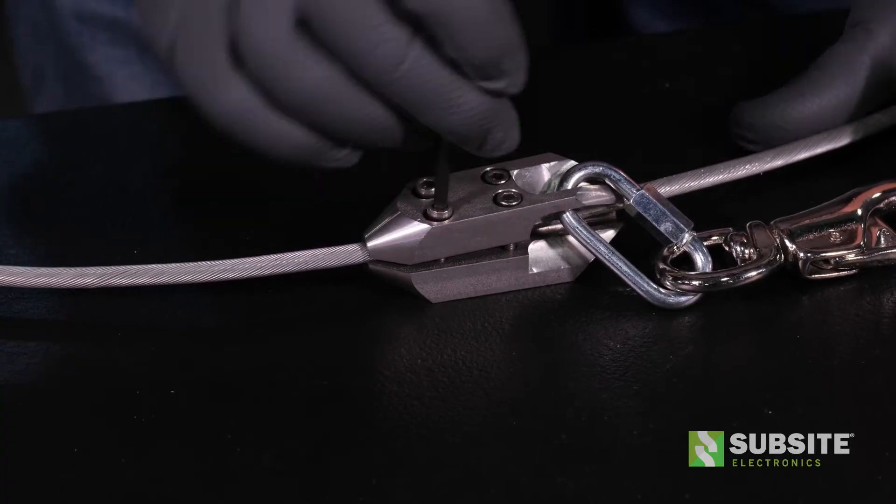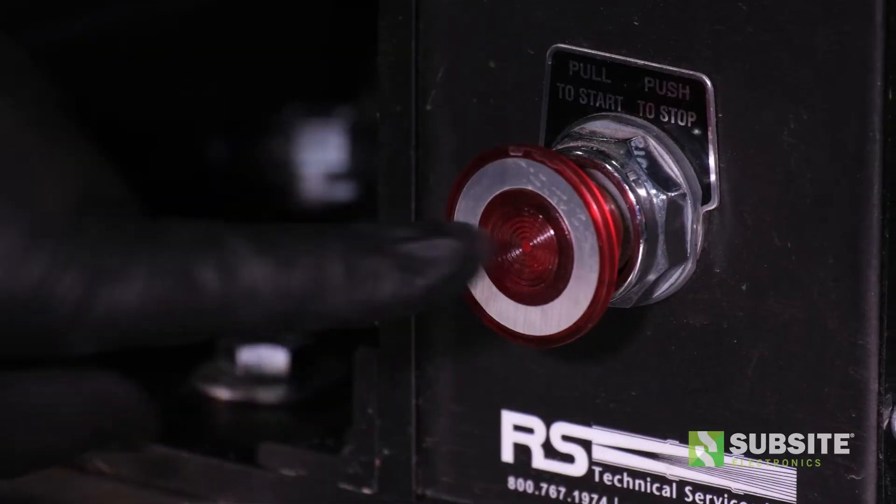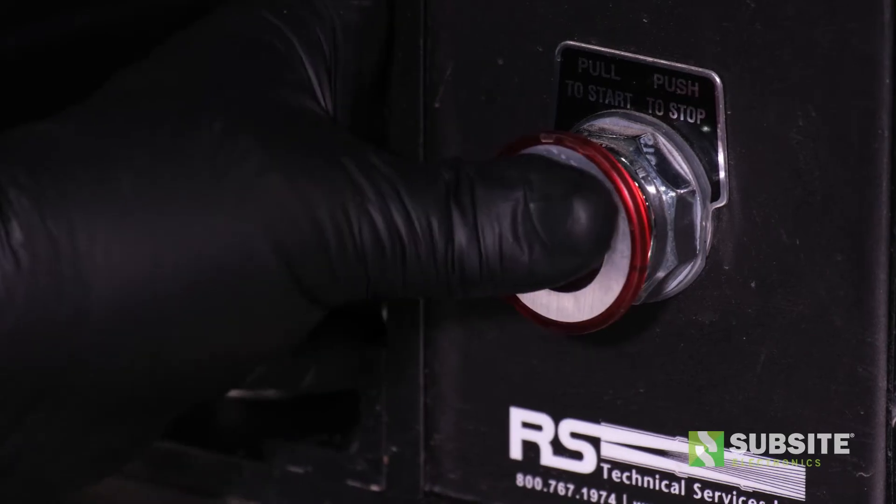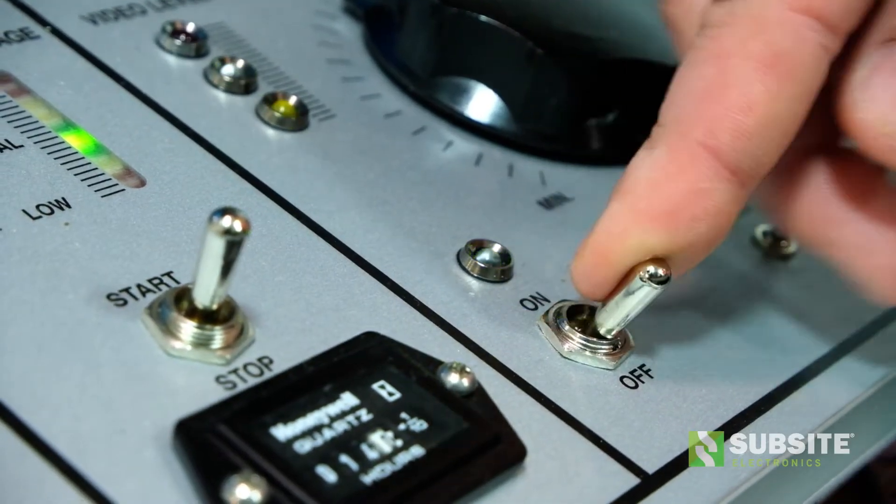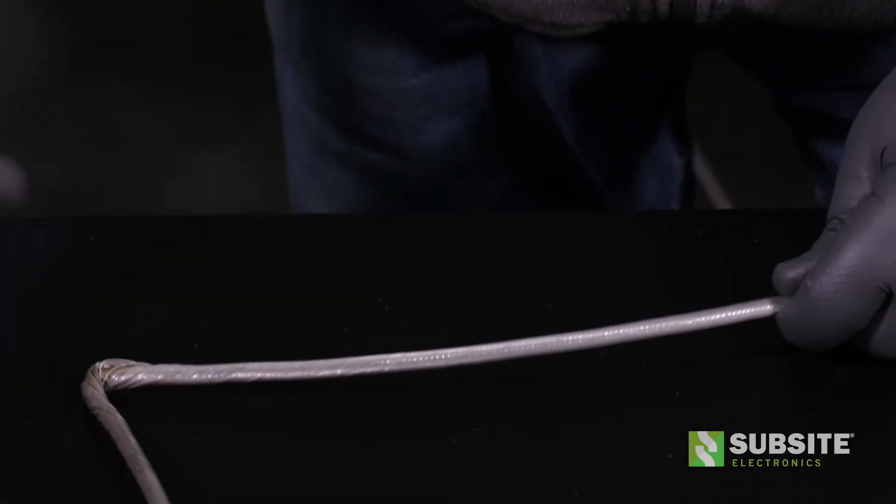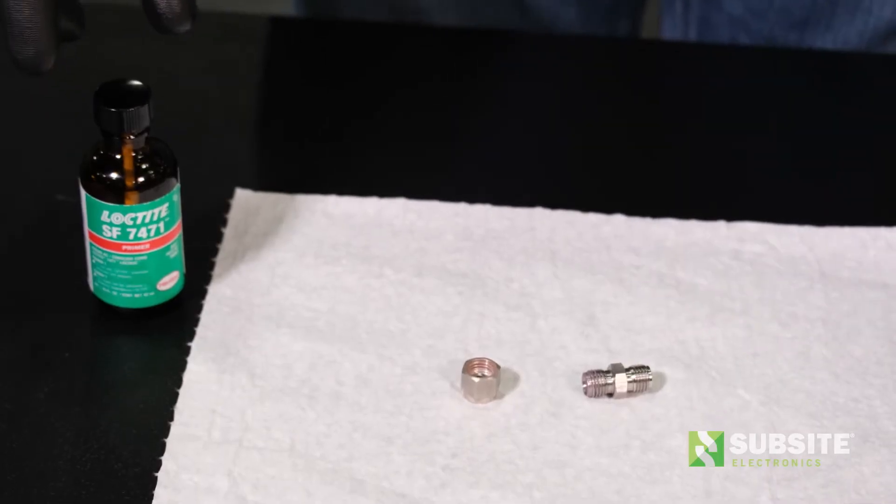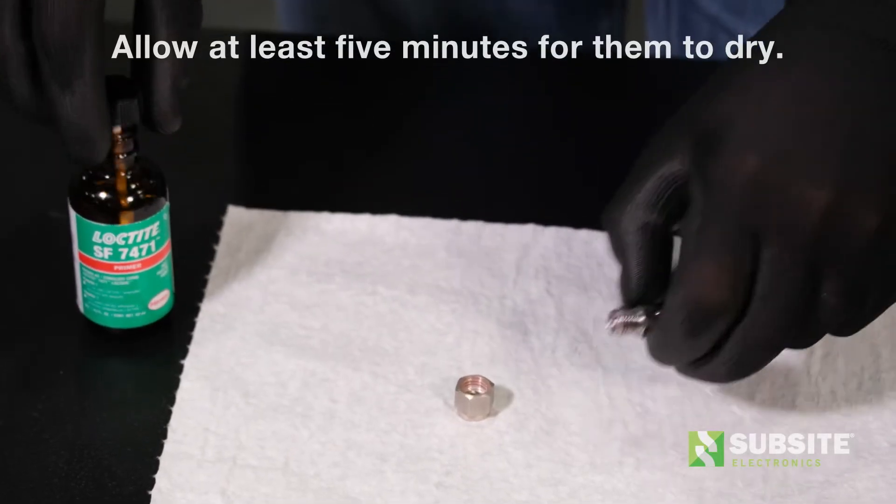Now, remove the cable grip using the 5/32nds Allen wrench. Press the e-stop button to power off the reel and then power off the controller. Clean and prep the cable. Use a shop towel to wipe the cable clean. If there's more significant debris, use a small steel brush to remove it. Apply Loctite primer to the threads on the ferrule body and nut.